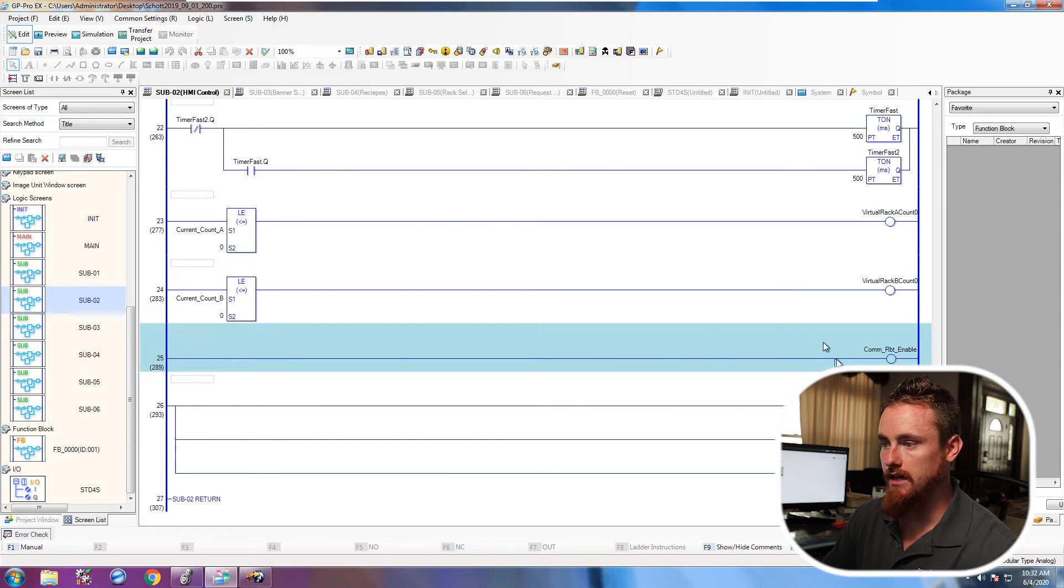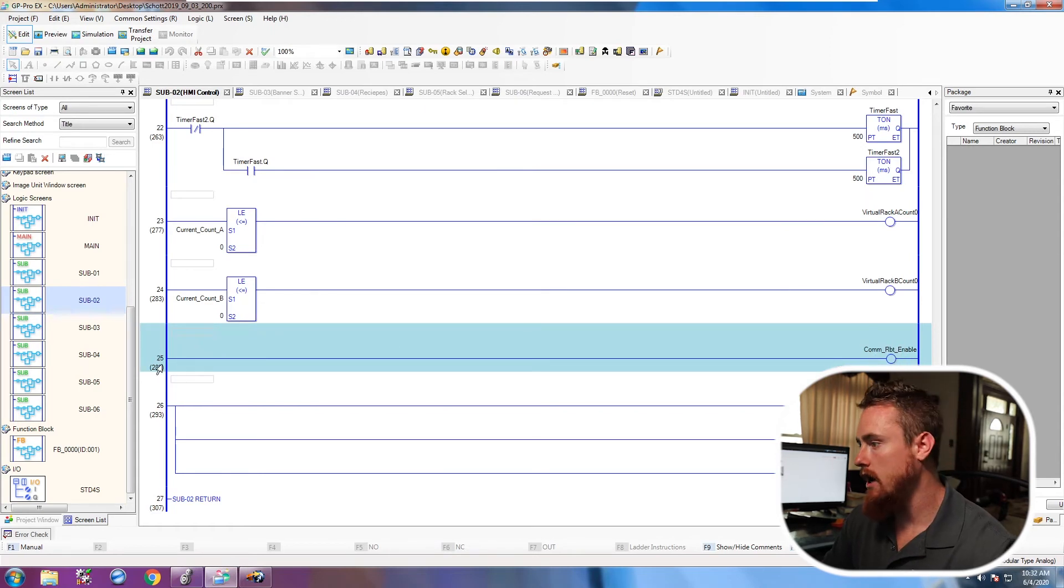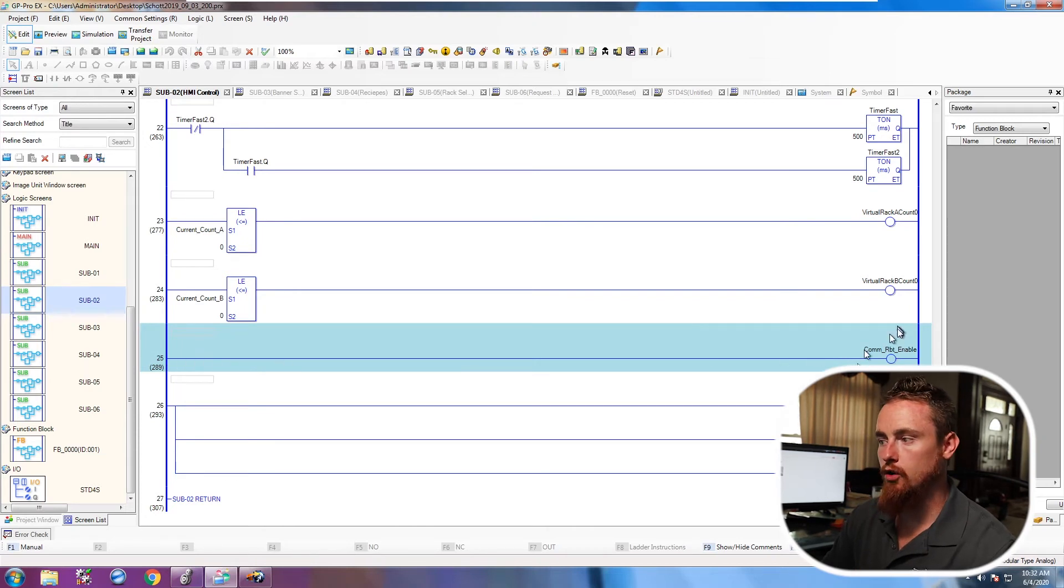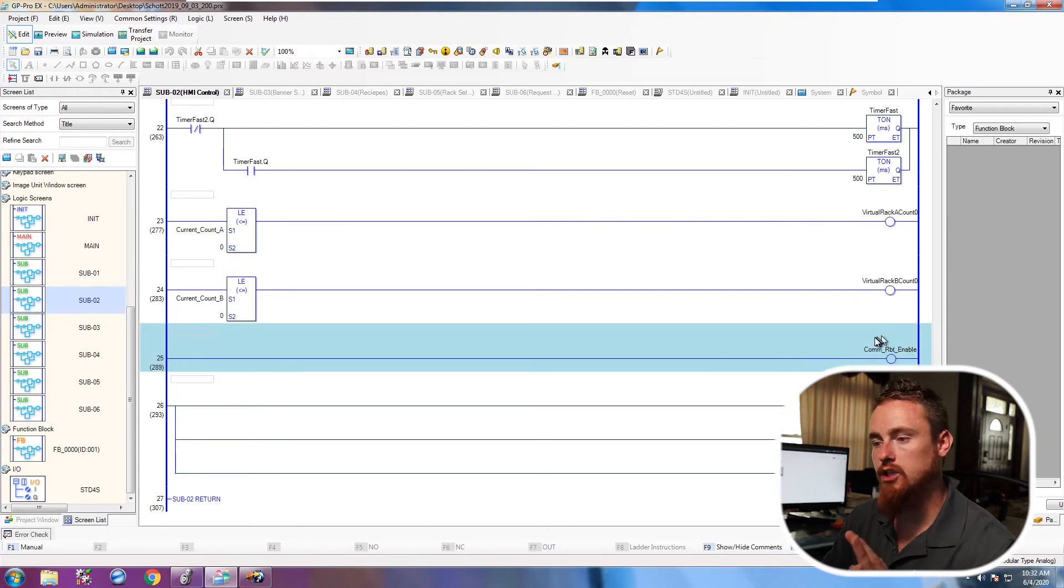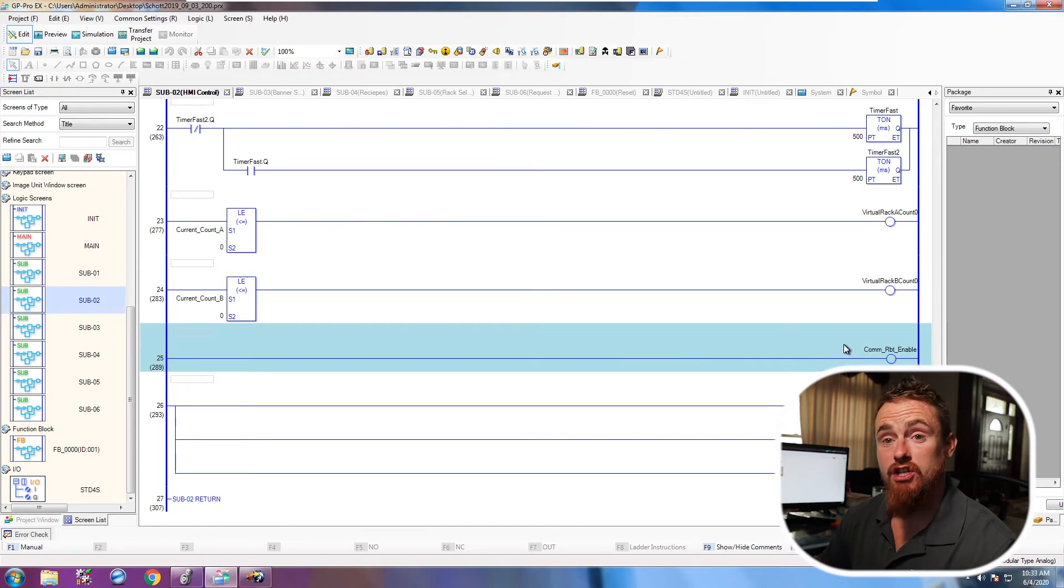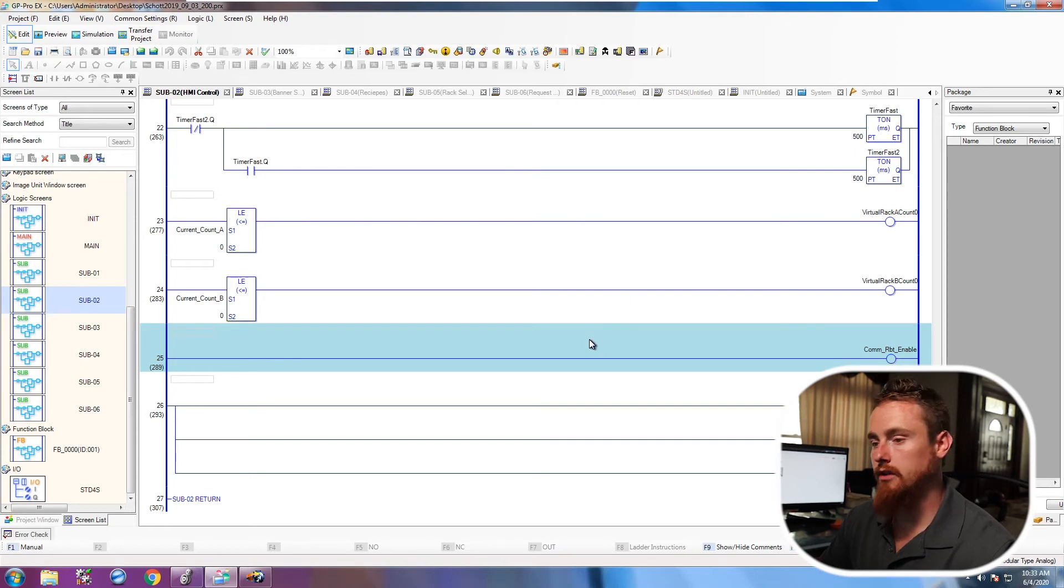So basically you're just going to put it in the logic as a coil, and then you're not going to put any bits in front of it. So that way, as long as the PLC code is running, then your bit's going to be enabled. It's going to be on, it's going to be true. And that should solve that issue. Now your message instructions should be running and everything should be working properly.